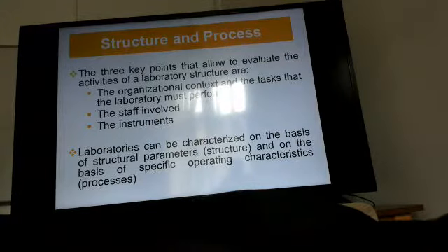So every day, the first thing to do before sample arrival is to check that the instruments work properly and calibrate the instrument. Calibration means that you will run early in the morning some samples that are called white samples.